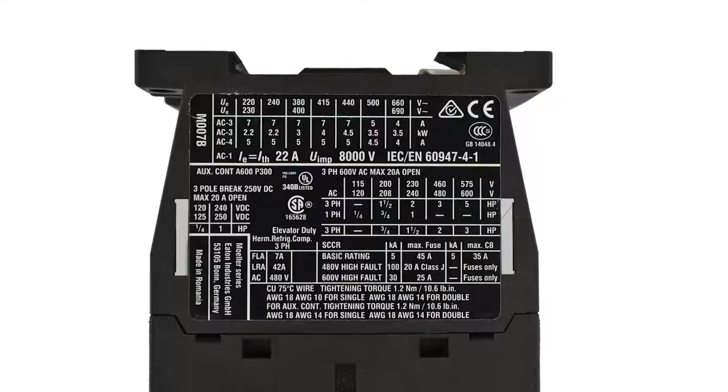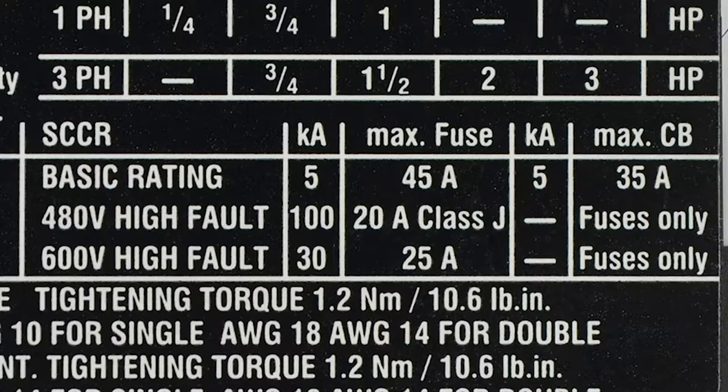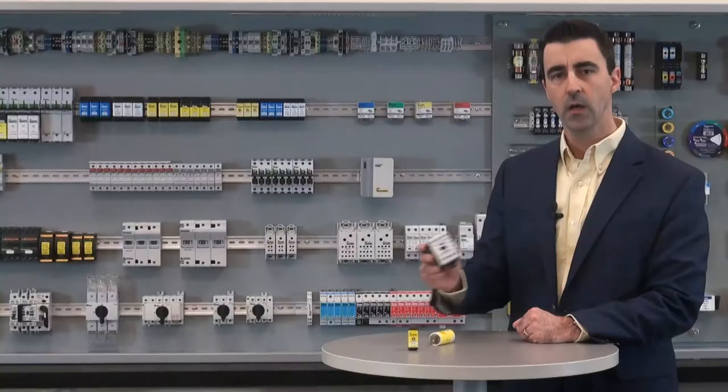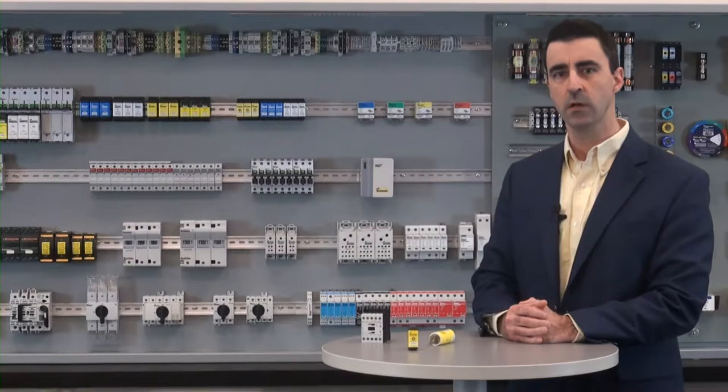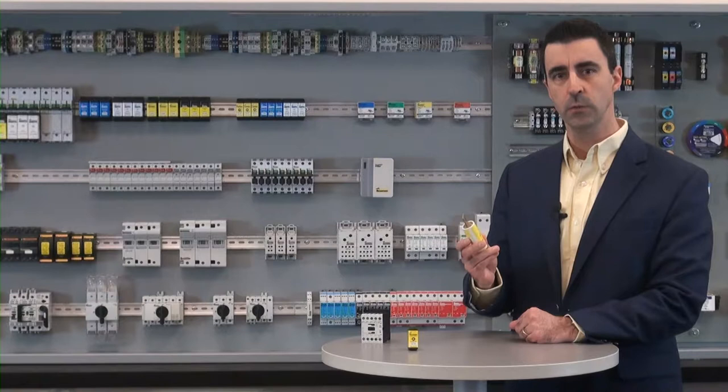An example is this contactor with a 5,000 amp default short circuit current rating. However, this same contactor has a 100,000 amp short circuit current rating when protected by a max 20 amp class J fuse due to its current limitation.